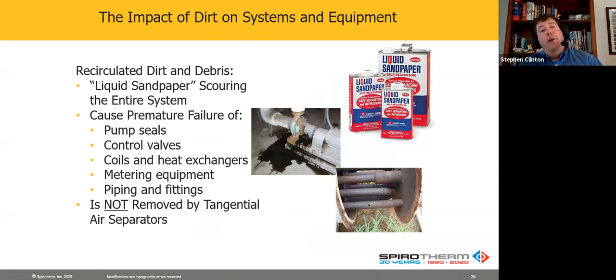Well, let's say it gets into a pump seal. How many times have you seen pump seals go down? Or control valves. Earlier in my career, we saw lots of globe valves, and you would see globe valves failing all the time because they're getting scored. As the seat tried to close, it would just scour it and it would be destroyed. Well, a lot of that is because that fine debris is moving at 30, 40, 100 feet per second. So that dirt is not doing anything to help the system at all.